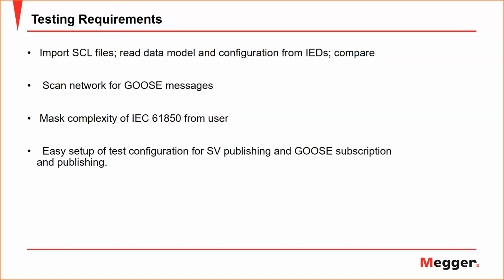And it does help to have an easy setup or a good knowledge as well, and a good device that can help you in publishing sampled value and GOOSE messages, either by subscribing or even publishing these messages. But there are a few things that are very important to understand when you are dealing with testing in an IEC 61850 environment. You have to really be careful when you are doing that, because once you start publishing anything, everybody will be able to see this. So you need to be very well aware of who is subscribed to this and in which mode these IEDs are at the moment.